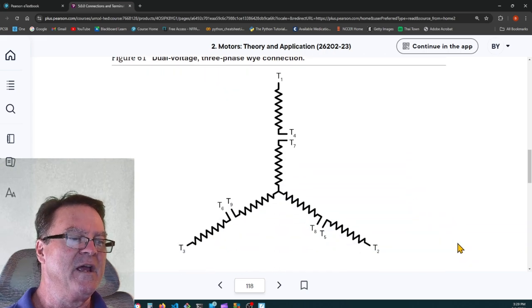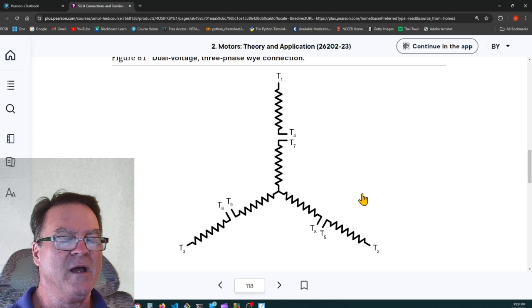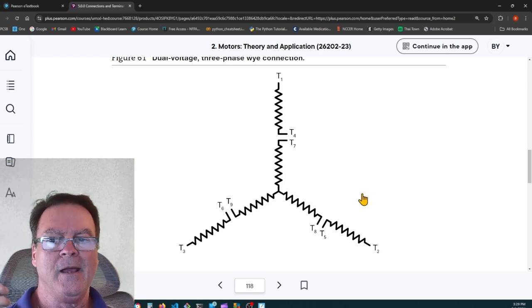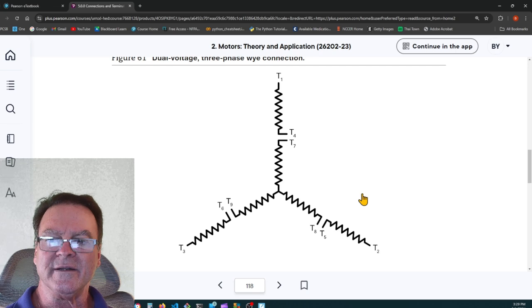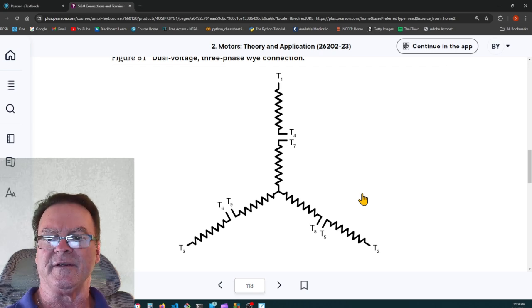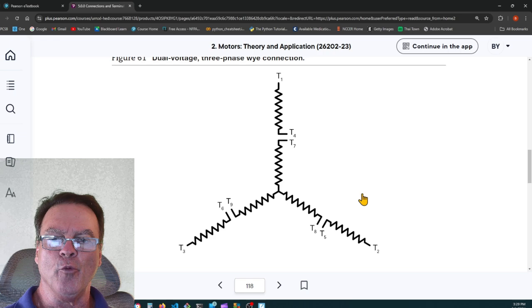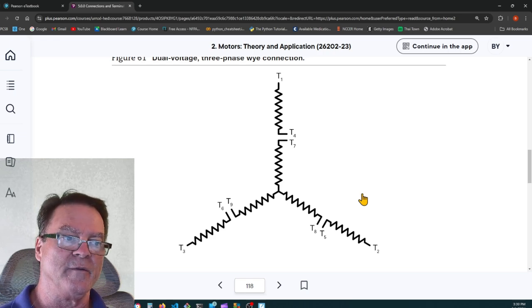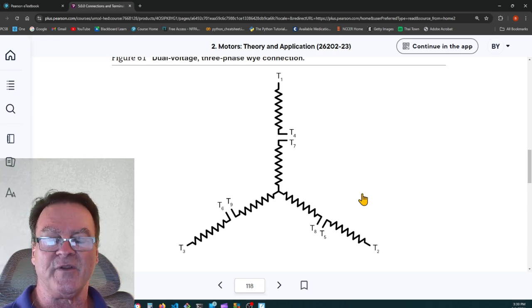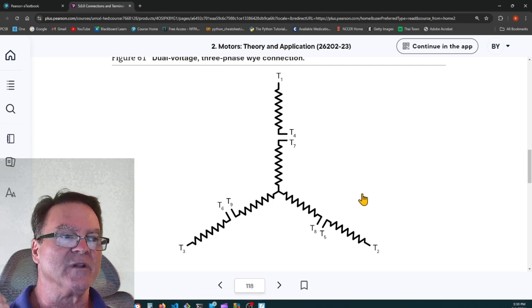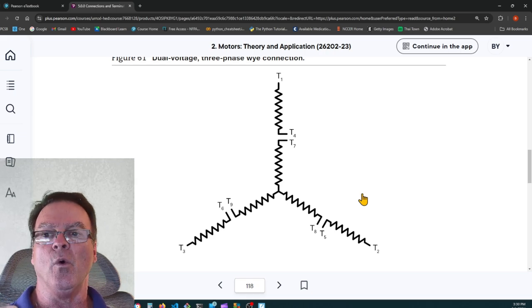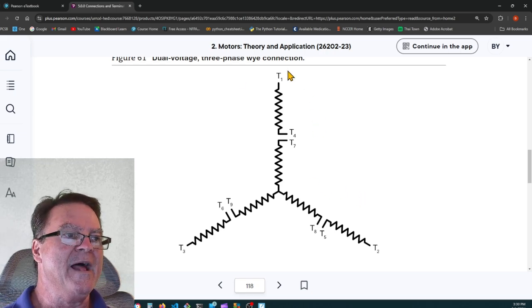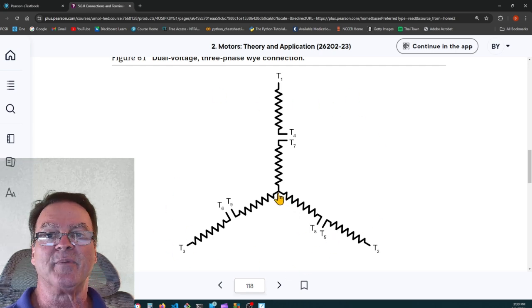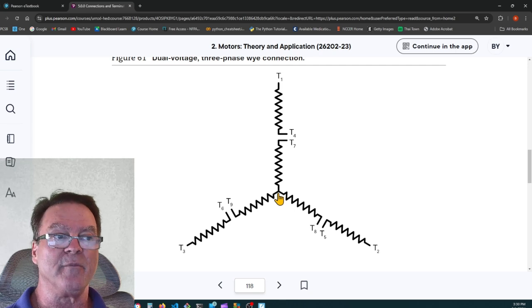So here's a Y-connected motor. Let me start by saying Y and delta are not real things. You'll never open up a motor or a transformer and see a delta, or see a Y. It's a pictorial representation of the relationships of the coils. So this would be what you'd see. Well, this is what would be typical of a Y-wired motor, WYE.